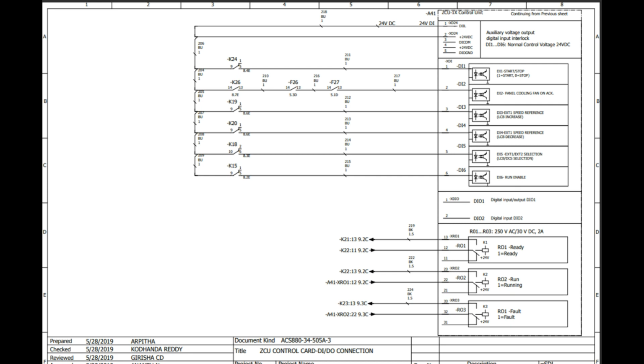Similarly, digital input 2 is cooling fan on acknowledgement. Digital input 3 is external speed reference from LCS, speed increase. Similarly, digital input 4 is LCS speed decrease, and digital input 5 is for LCS or DCS selection, local: whether it has to run from local or from control. And lastly, this is important, digital input 6 is run enable, and 24 volt has to come from K15. So what these K15, K18, K20 are, we will see in the next slide to come.